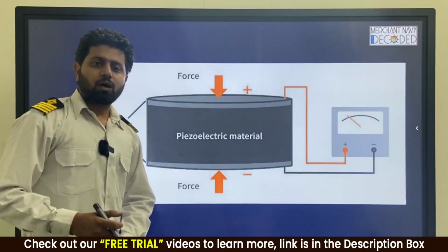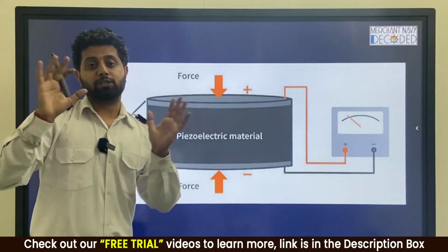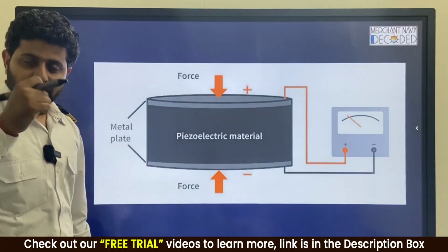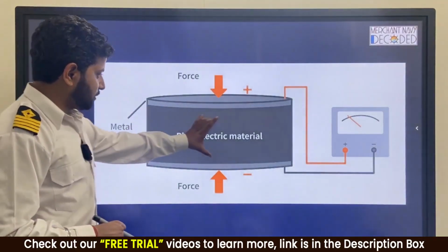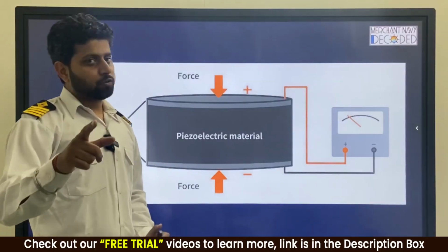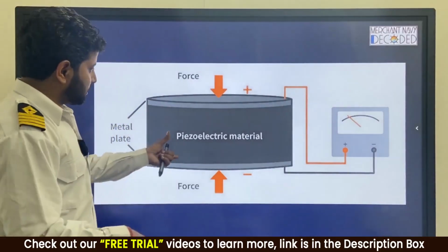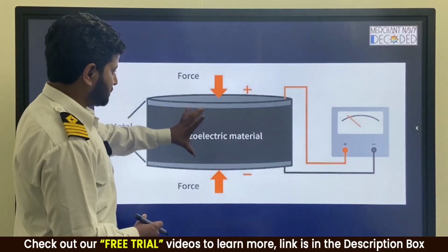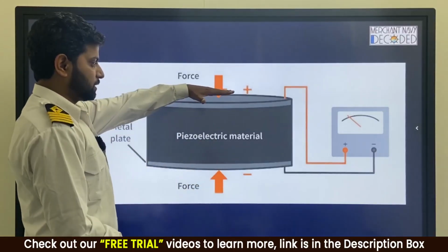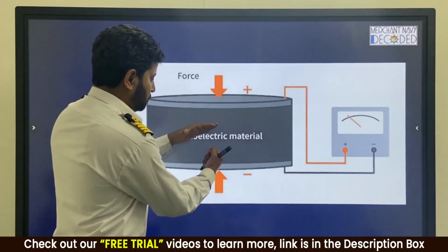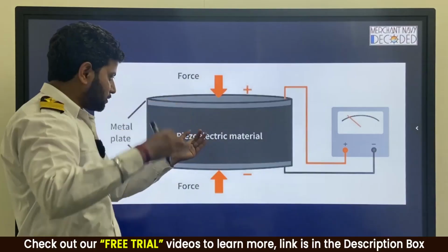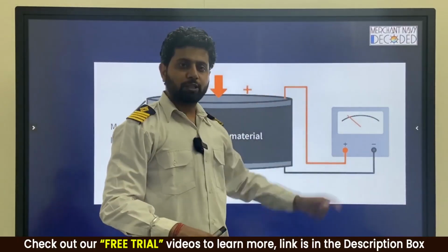Let's move ahead. So now let us discuss what kind of pressure transmitters can be there. One is the piezoelectric type. So this is a piezoelectric material fitted inside. If you have not watched the video on piezoelectric sensor, please watch it. So it can be quartz over here. The pressure is acting say from one end. This is a fixed plate. What will happen? This force will put a pressure on the piezoelectric material and a certain voltage will come out.